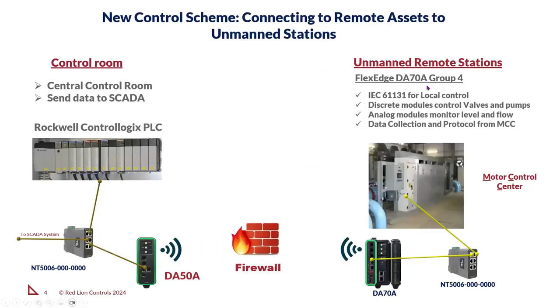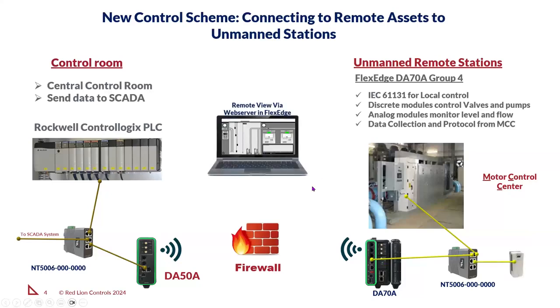In the unmanned stations, we simply imported the Graphite HMI program to one of our FlexEdge DA70A Group 4 devices, which has IEC 61131 ladder logic, function block, statement list for local control built in. We added on discrete I/O modules and analog I/O modules, as well as the FlexEdge came in populated with a 4G cellular sled and a Wi-Fi sled, which came in handy because we have some really cool features built into our Graphite HMIs and FlexEdge Group 3 or 4s.